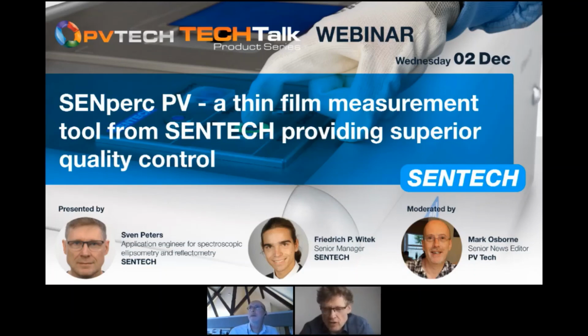There is an official lifetime for these lamps, which is about 2,000 hours. But from the praxis, we know that you can also use it even much longer. So there's no need to really replace it after 2,000 hours. We're looking for other things like the stability of the lamp. When this is dropping, then we have to replace it. Right, got it.